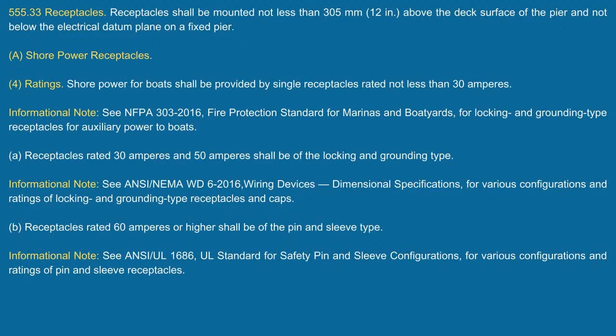Also, it's interesting when you're looking at the receptacle, that shore power receptacle - when you look at 4A, it tells you that receptacle is rated at 30 amps and 50 amperes and shall be of the locking and grounding type, meaning it's going to lock in. There's a reason the receptacles are designed a certain way. Basically what they're telling you is, as the owner of that slip, cord and plug connecting that, you're going to be doing that to the unit that's there, that's providing the shore power. And that's the reason there's no GFCI protection.